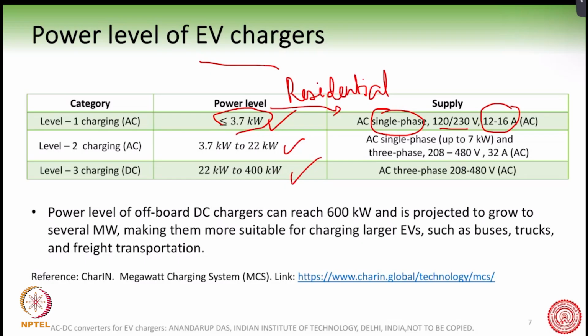On the other hand, level 2 charging goes up to 22 kilowatt, which cannot be provided by a single phase supply. By changing the circuit breaker you can go up to about 7 or 8 kilowatt maximum on single phase, beyond which the grid operator will not allow you to take such high power from a single phase outlet.